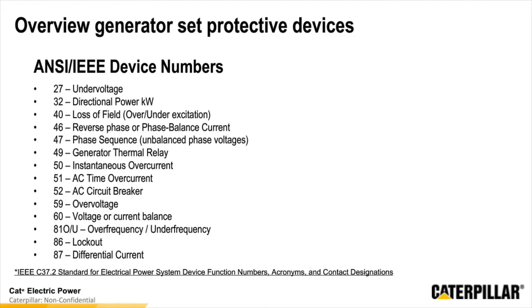So the next thing that we're going to talk about is the relays within the system and what relay protectives we may have within a typical generator set system. ANSI IEEE device numbers are typically what we see within the system. These are a list of things that we would see with a generator set. The list here has the ANSI IEEE device number associated with it. If you'd like a complete list of the different devices that are available, you can see the IEEE C37.2 standard for electric power system device function numbers, acronyms, and contact designations.